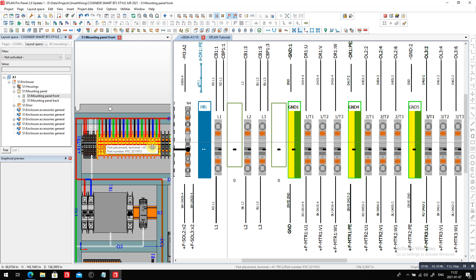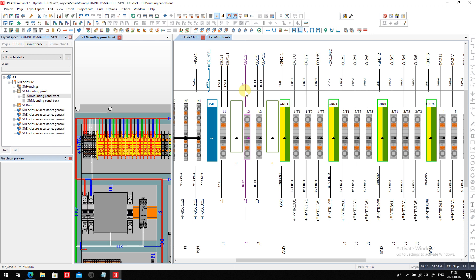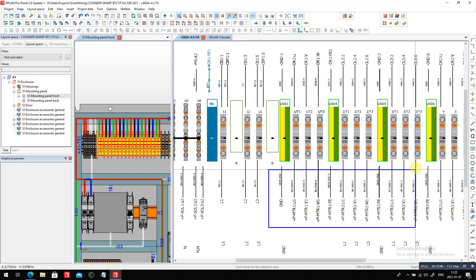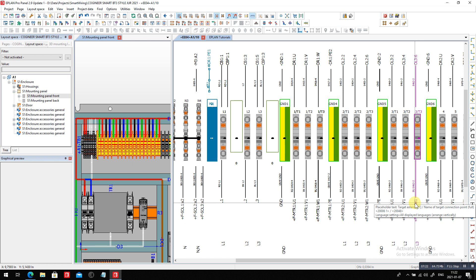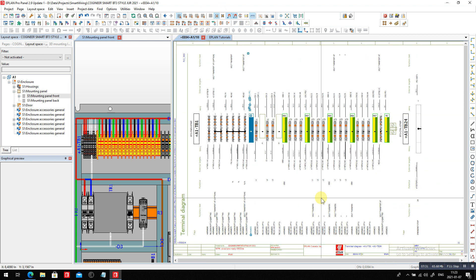So the intention behind the terminal diagrams, for those of you who do not know, is to not only put together the terminal, but also to connect the terminal strips very efficiently and even to cross check them because very often, what is on the bottom side here is actually what is out in the field, most likely motors, sensors, solenoids and something like that. This technique, very graphical technique in Europe is very old, it's called a terminal diagram, terminal connection diagram.